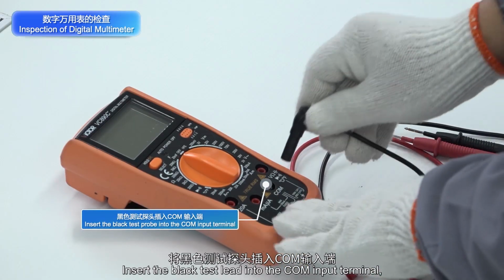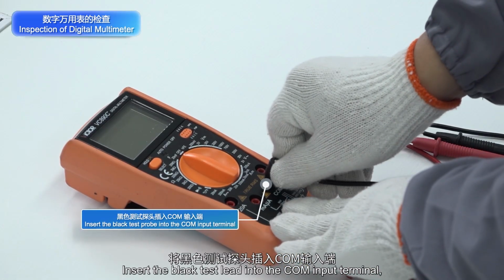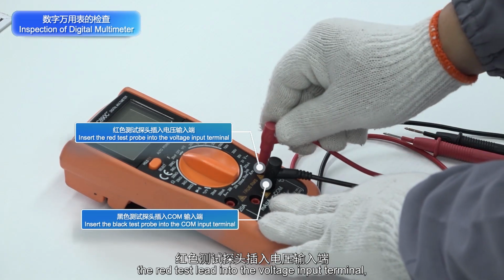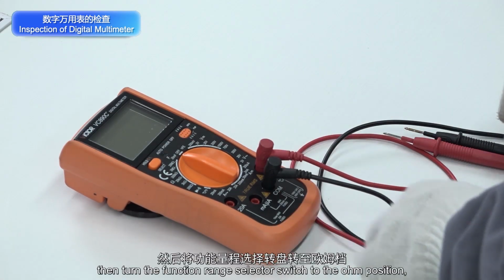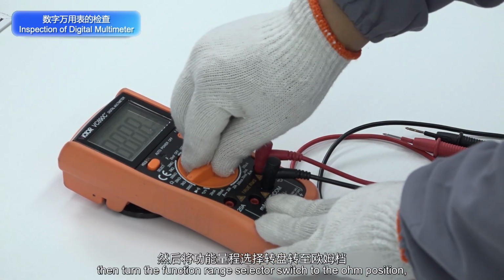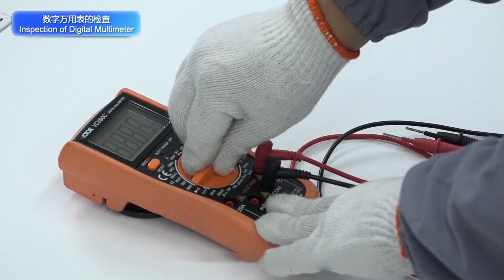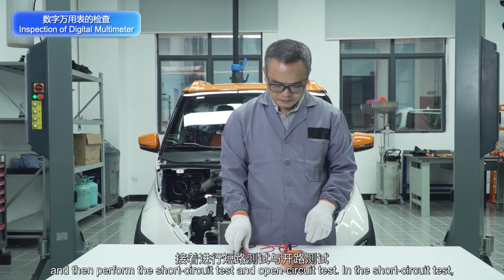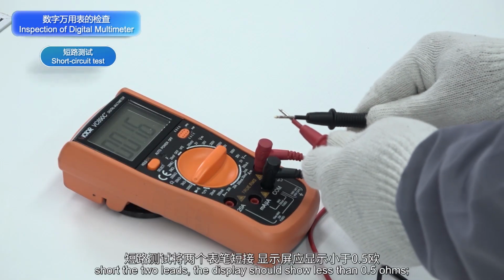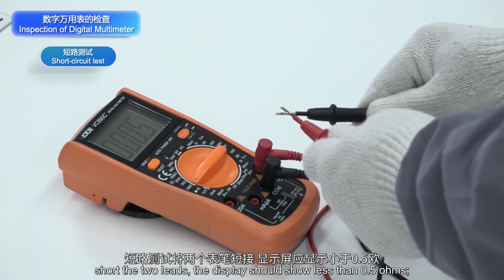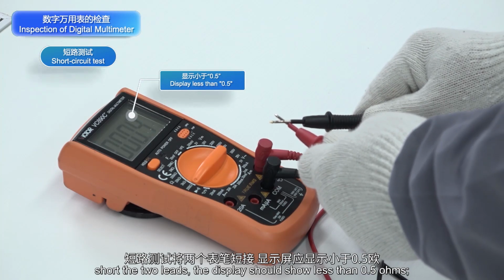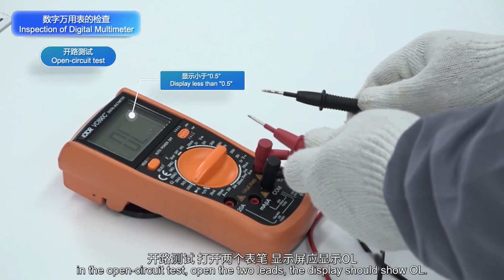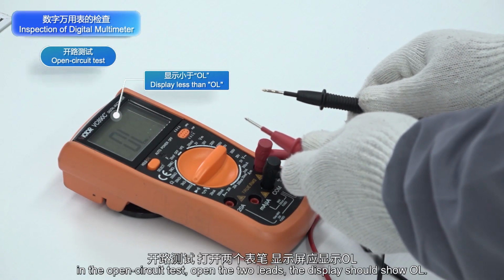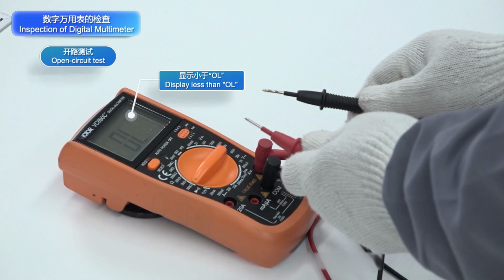Insert the black test lead into the COM input terminal, the red test lead into the voltage input terminal. Then turn the function range selector switch to the ohm position, and then perform the short circuit test and open circuit test. In the short circuit test, short the two leads, the display should show less than 0.5 ohms. In the open circuit test, open the two leads, the display should show OL.